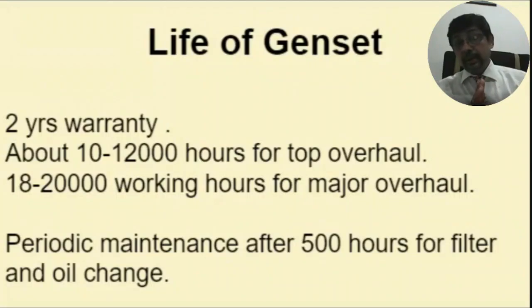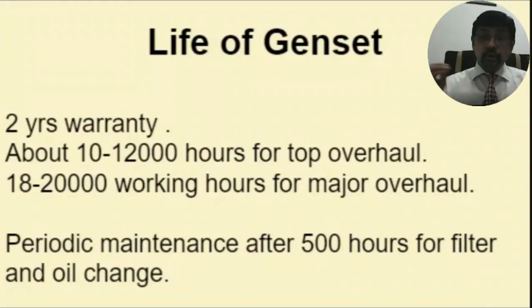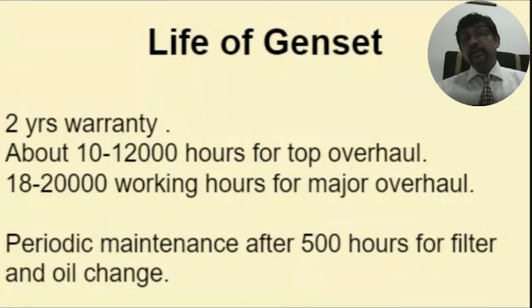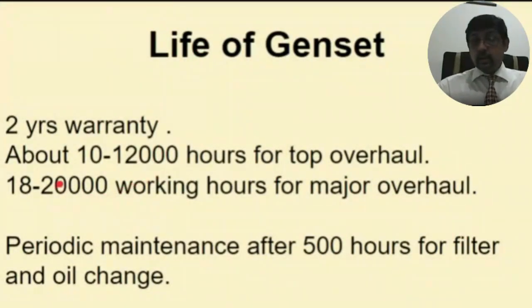But at 18 to 20,000, it's a major overhaul where the engine is totally stripped down. That means the crankshaft, the pistons, the con rods are all opened and checked, whether they are reusable or not, because the engine, which rotates at 1500 RPM, rotates with these three or four major things, that is the con rod, camshaft or connecting rods. These are basically the pistons, cylinders. These are the things which are the life of that engine. So that is checked after 18 to 20,000 hours as recommended by the manufacturer.